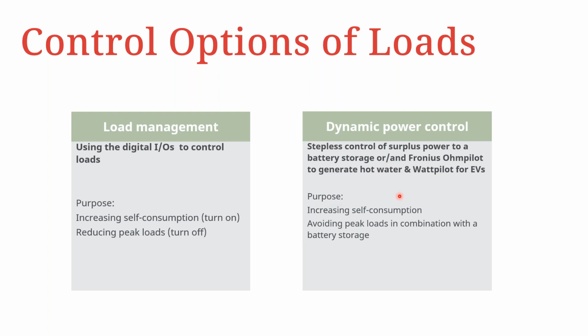And therefore, the purpose here would be likewise to increase the self-consumption and avoid peak loads in combination with battery storage, because the battery storage can also become a buffer. If you have a load that is consuming more than the PV production at that particular moment, then whatever balance of power is required can be taken out from the battery storage before you go on to consume any power from the grid.